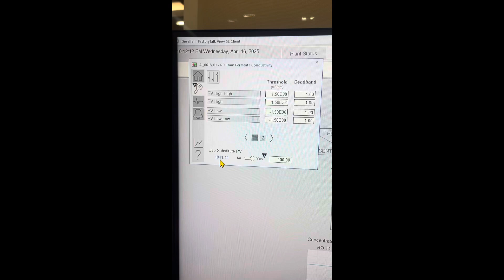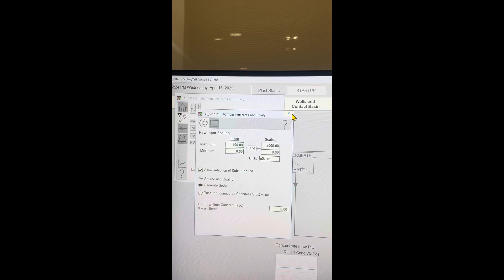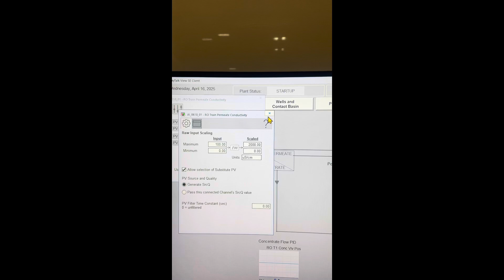And as you can see, now that's really close, if not the number that's reading on the Sc200 out in the RO building. So I'm actually going to go ahead and eventually change this to 600, as well as the upper limit to 600 again, for the permeate conductivity probe out there, because that's a good operating range for when the train first turns online.